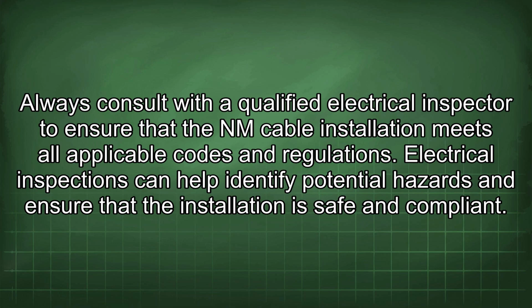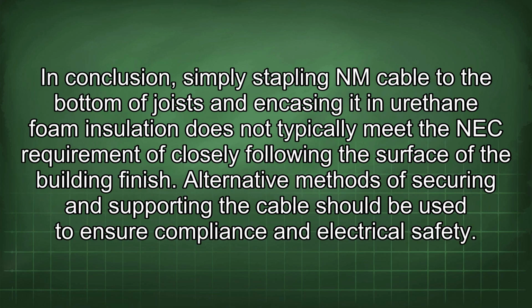Electrical inspections can help identify potential hazards and ensure that the installation is safe and compliant. In conclusion, simply stapling NM cable to the bottom of joists and encasing it in urethane foam insulation does not typically meet the NEC requirement of closely following the surface of the building finish. Alternative methods of securing and supporting the cable should be used to ensure compliance and electrical safety.